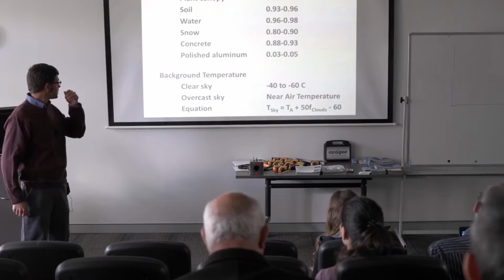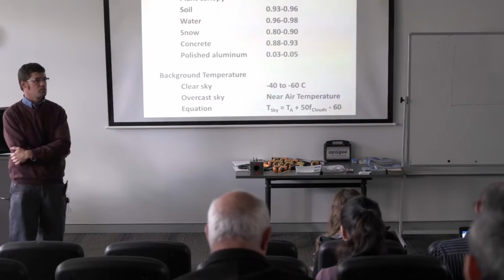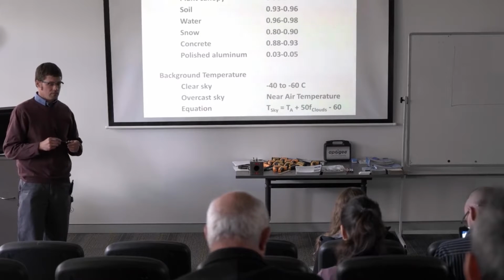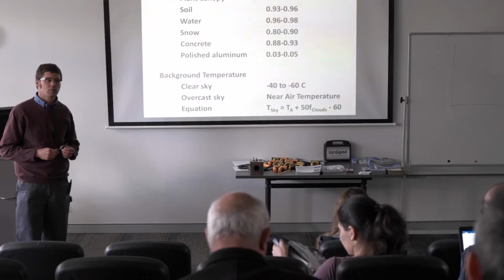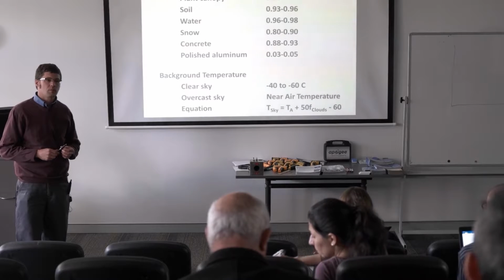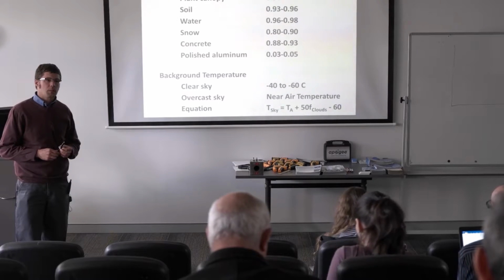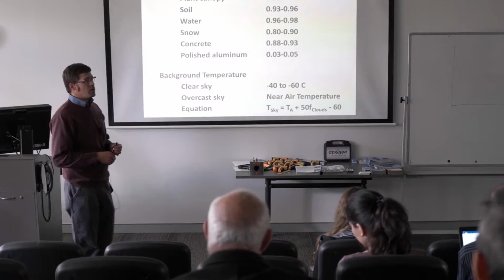They act like it's just a simple dial, you can just correct for this, and that drives people that know what they're doing crazy, because it confuses the issue. You can't just take a dial and correct for emissivity.